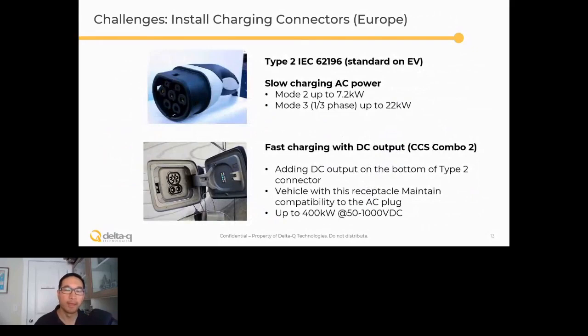So the plug looks a little different for the standard EV plug in Europe and much of the rest of the world. It's called the Type 2, IEC 62196. This is a mode 2 up to 7 kilowatts, and a mode 3 with 3-phase up to 22 kilowatts. Delta Q can help you if you think you can get 3-phase, but as I understand, in Europe it's somewhat uncommon — most of it is going to be mode 2.